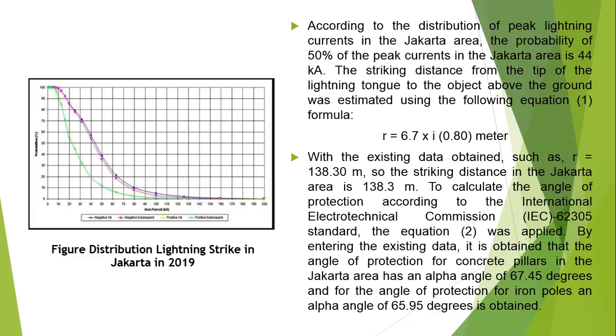By entering the existing data, it is obtained that the angle of protection for concrete pillars in the Jakarta area has an alpha angle of 67.45 degrees, and for the angle of protection for iron poles, an alpha angle of 65.95 degrees is obtained.